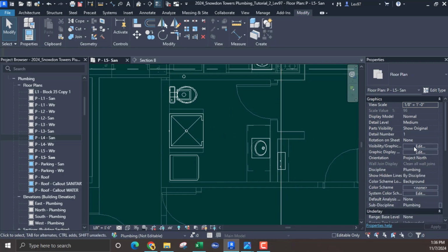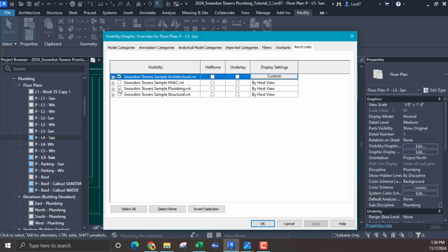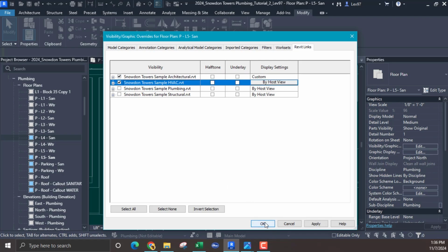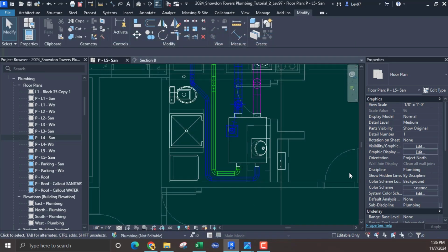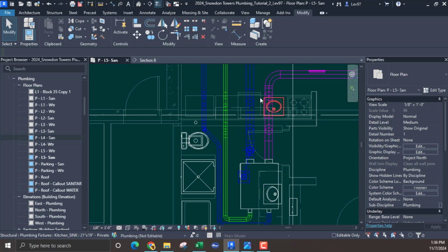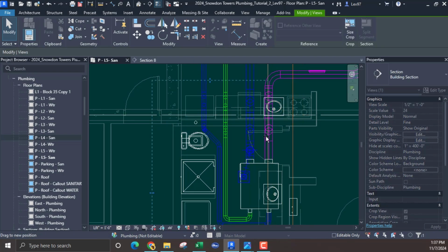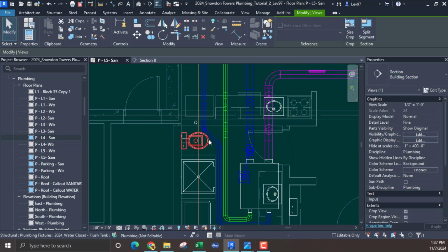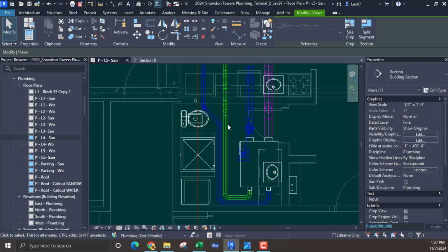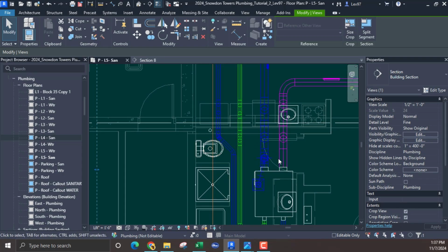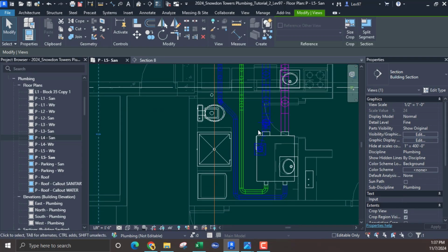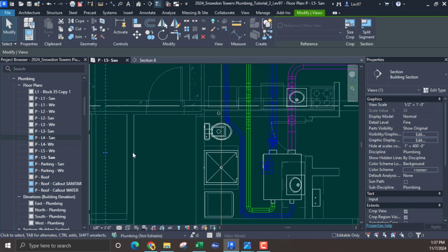So if I turn on the view, let's turn on HVAC. Okay, so it's back here. It's not even close. It's way back here somewhere. But I'm picking it up because my zone is so large. So I want to decrease that as much as possible. I could always turn on and see if I have any kind of, see what's the best route. And that's another option you can do. But in this case, I'm gonna tighten this guy up as much as I can.